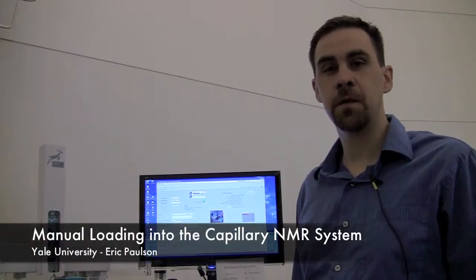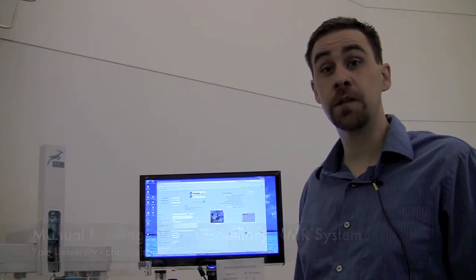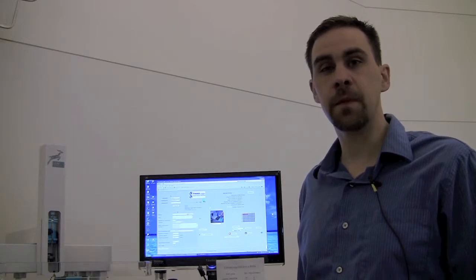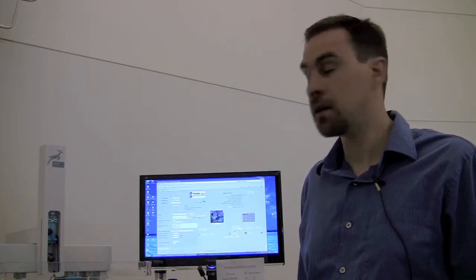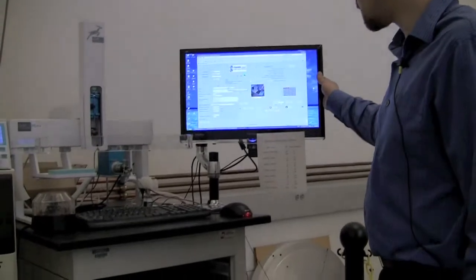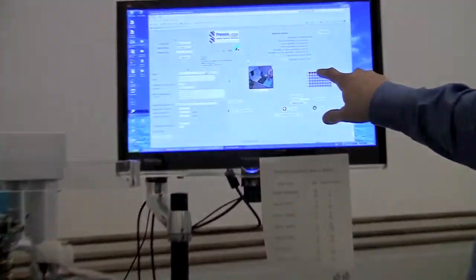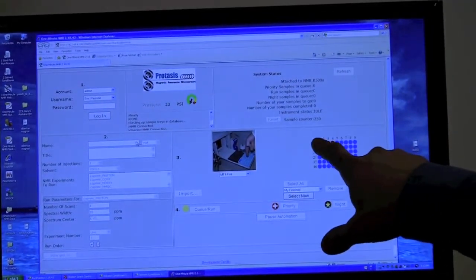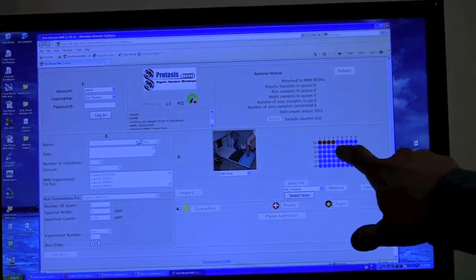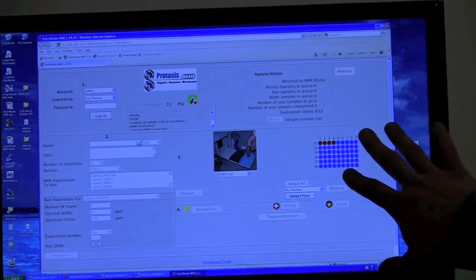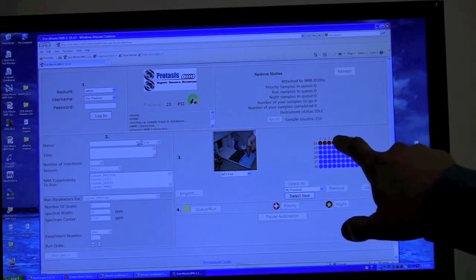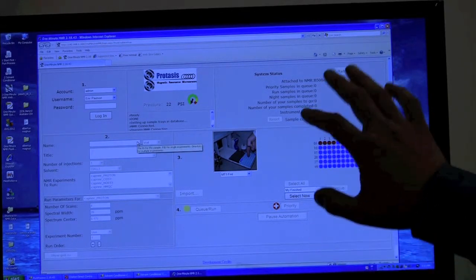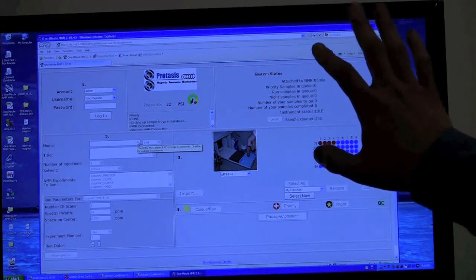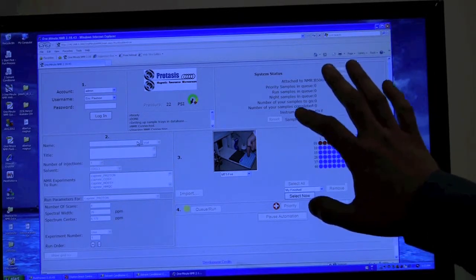So this is an explanation of how to do the capillary NMR with manual injection, which you can use any solvent and you can recover your sample, unlike with the automation system. So the first step is to make sure that the automation is not running. Come to the screen of the automation system and check on this part right here. If they're all red or bluish purple, they're not running. If there's anything that's green, yellow, or bright purple, something may be running, and you should make sure that everything is stopped before you go to the next step.